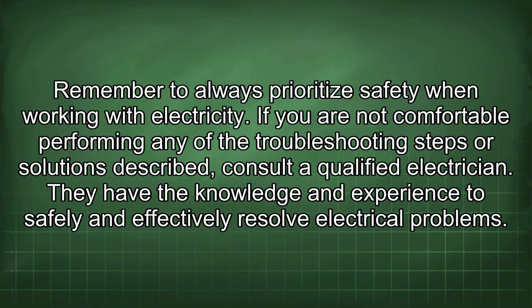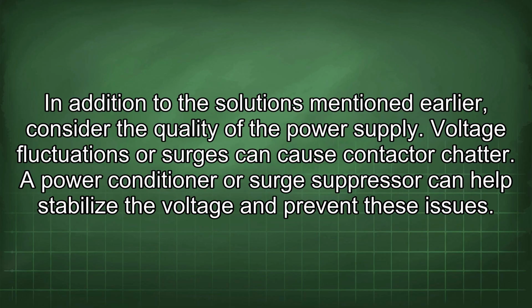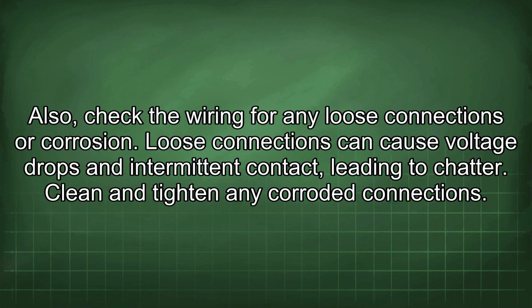They have the knowledge and experience to safely and effectively resolve electrical problems. In addition to the solutions mentioned earlier, consider the quality of the power supply. Voltage fluctuations or surges can cause contactor chatter. A power conditioner or surge suppressor can help stabilize the voltage and prevent these issues. Also, check the wiring for any loose connections or corrosion. Loose connections can cause voltage drops and intermittent contact, leading to chatter. Clean and tighten any corroded connections.